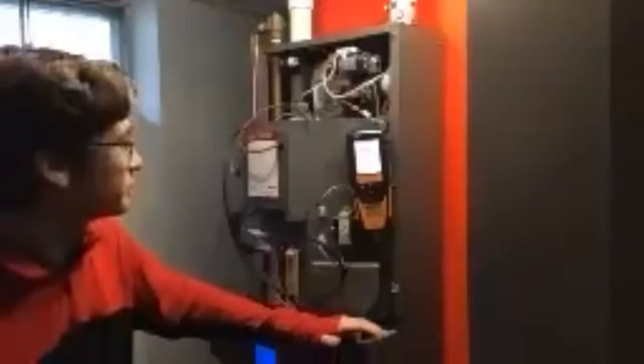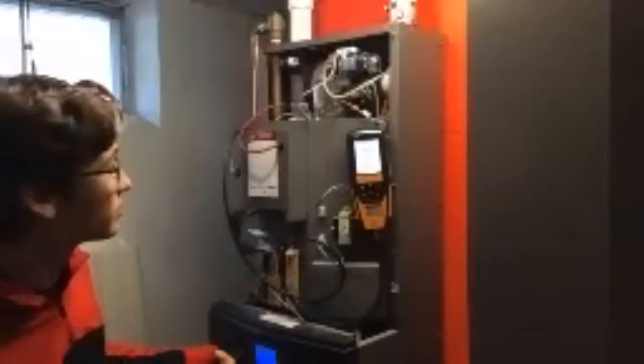So right now the numbers on here are going up, and in a little bit they'll start to stabilize. The one that we'll be looking at right now is in the third spot, which is the parts per million CO. Right now it's at 31, and it looks like it's stabilizing around there. Now it's starting to go up one by one. It's at 33. And once that stabilizes, right now it's stabilizing at around 35 parts per million.